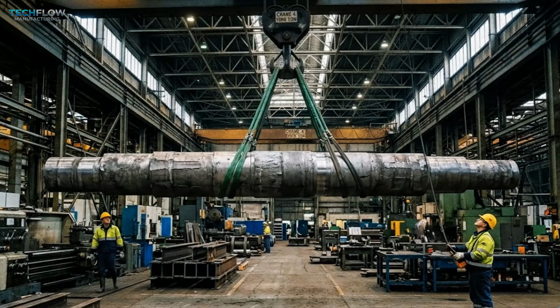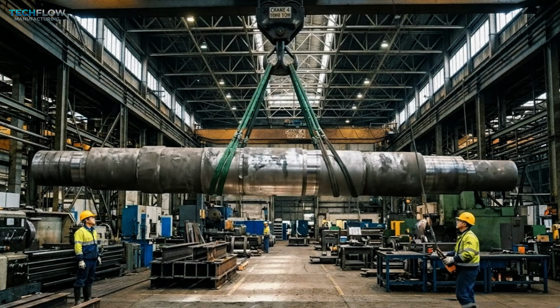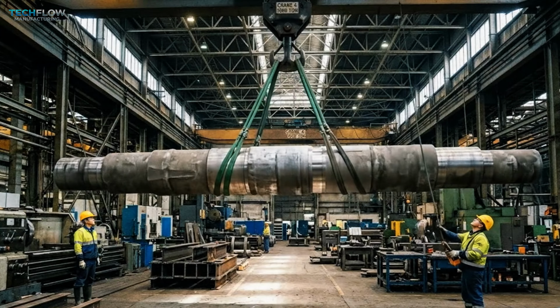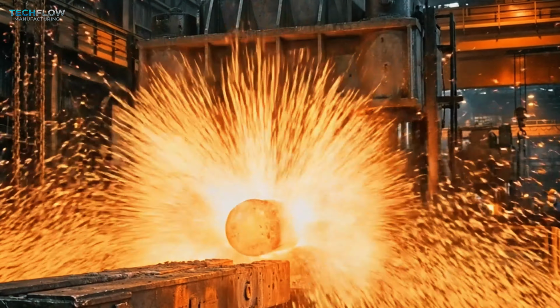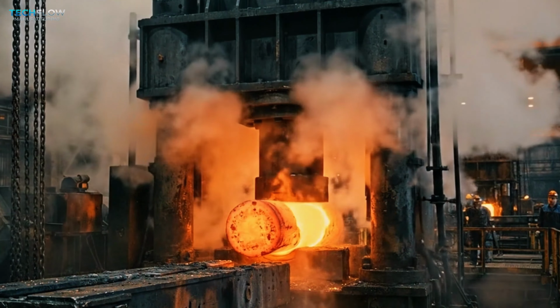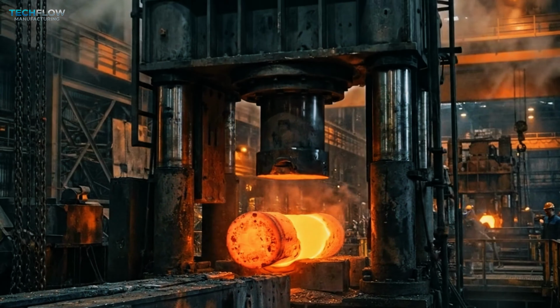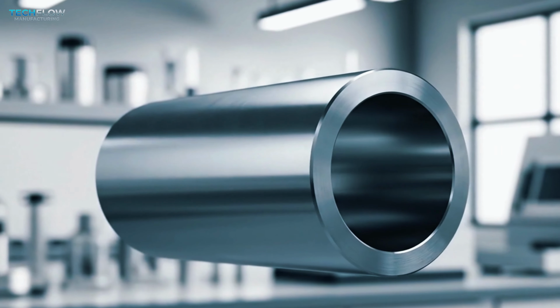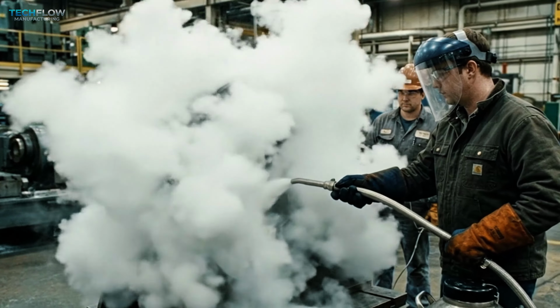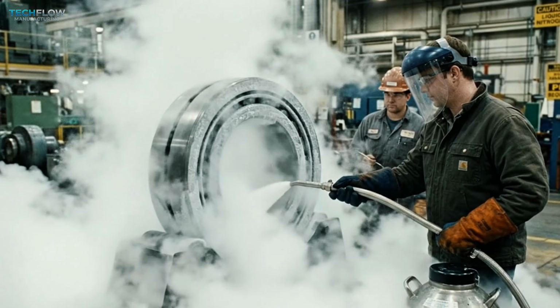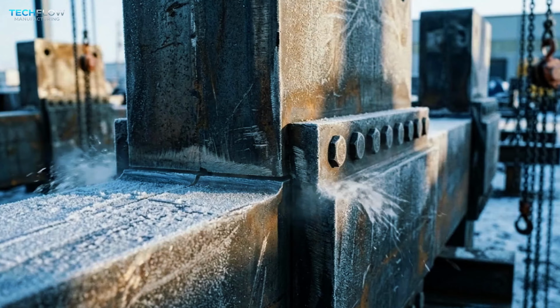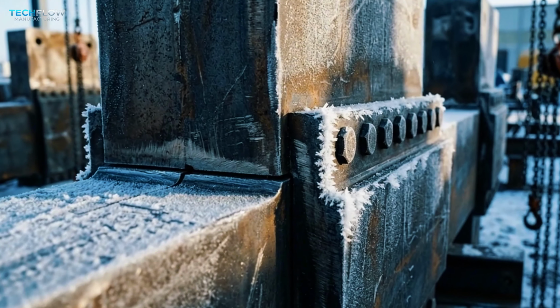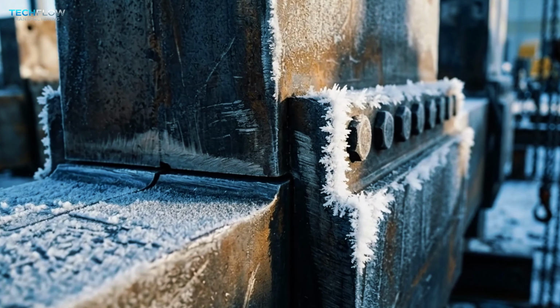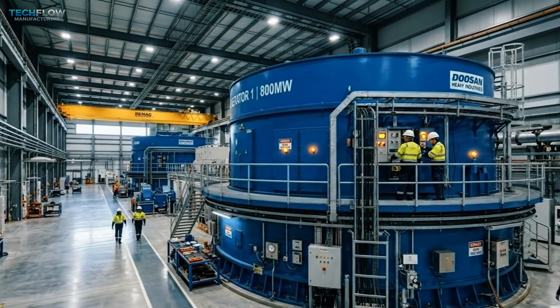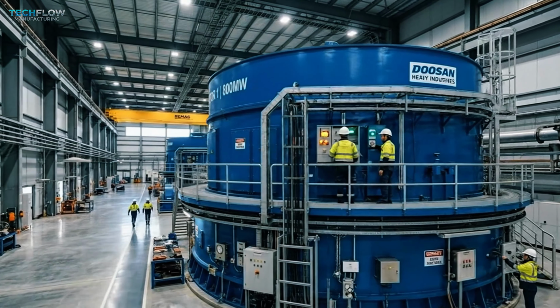The shaft, a solid forged steel cylinder weighing 500 tons, is the spine of this mechanical beast. Forging this shaft requires a 15,000-ton hydraulic press to align the metallic crystalline structure for maximum strength. Any impurity in the forging process could lead to catastrophic fatigue failure during high-speed rotation. At the assembly floor, we use liquid nitrogen to shrink-fit the bearings into place with absolute thermal precision. As the metal cools and contracts, it locks the components together with a force that no mechanical bolt could ever match. Above the turbine sits the generator, a massive electromagnetic heart that converts kinetic energy into raw power.